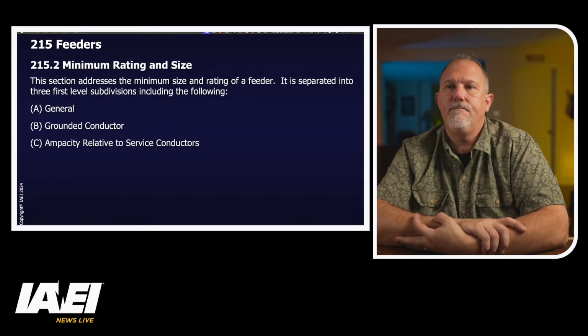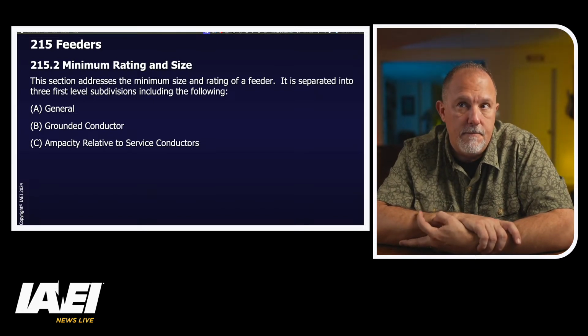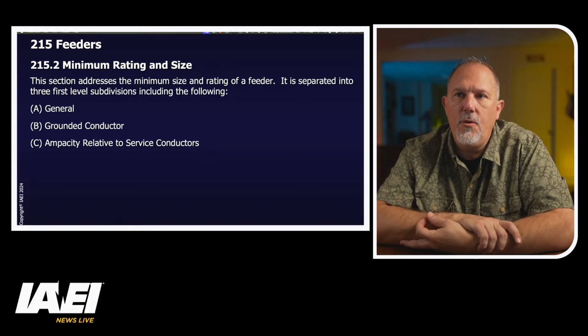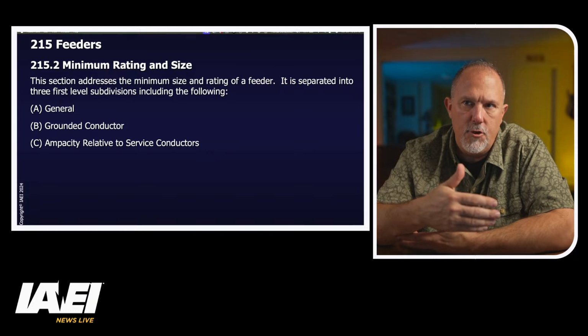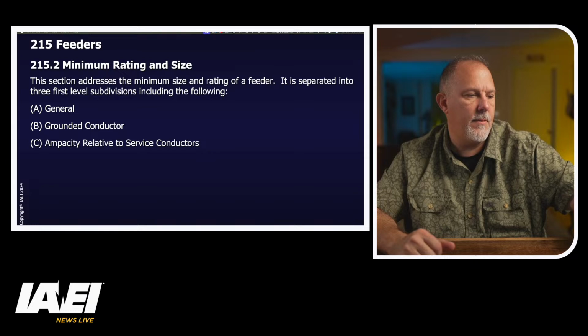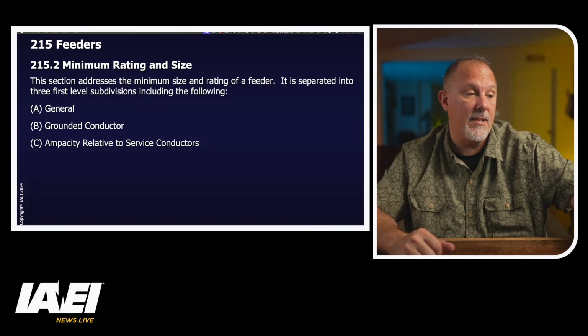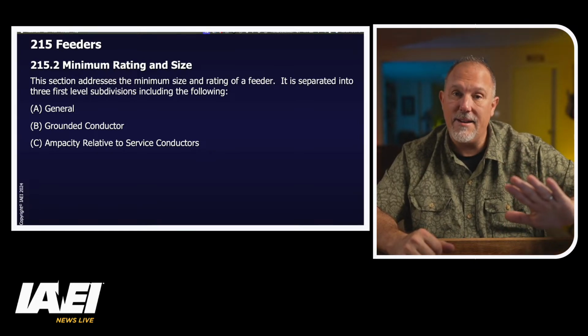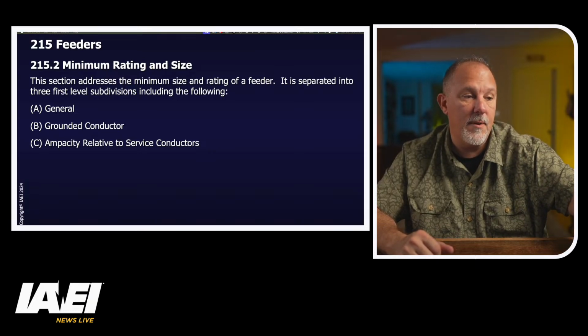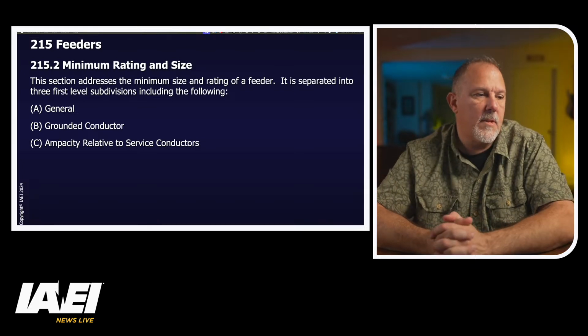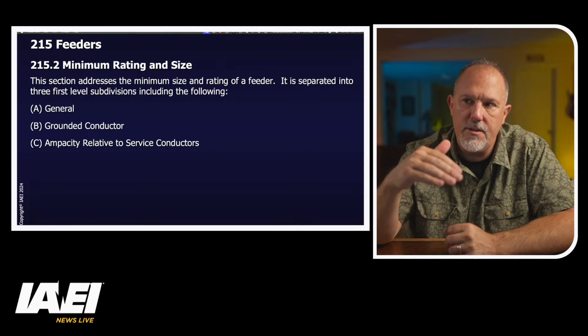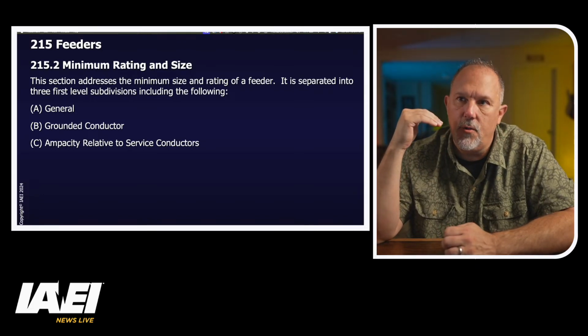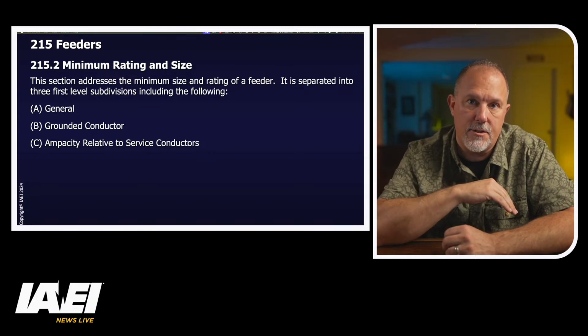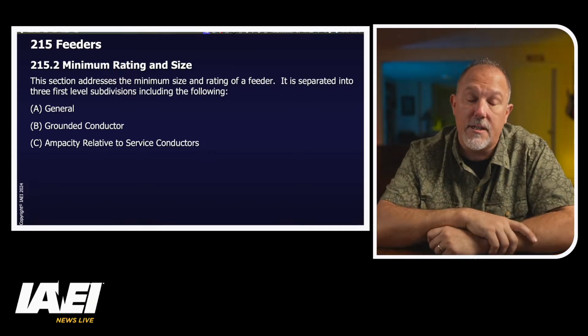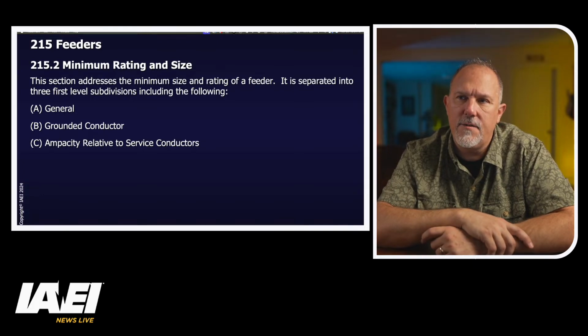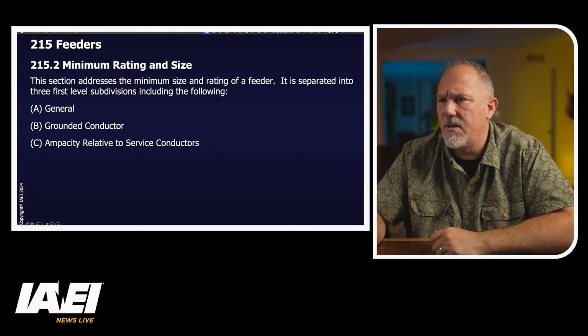Okay, let's move on. Minimum rating and size of a feeder. So you have your general requirements in A, and let me just bring up my iPad. This is the nice thing about NFPA LiNK and having an iPad. I can bring up the language over here so I know what I'm talking about. So if you look at 215.2, A is your general requirements. B is your grounded conductor. They talk about the sizing of the grounded conductor. That's what we quote unquote call neutral, but we call it a grounded conductor because it may not be a neutral point. And then you have your ampacity relative to service conductors, and we're going to take a look at that. Let's take a look at some comments first.